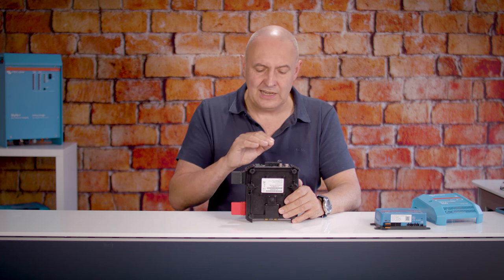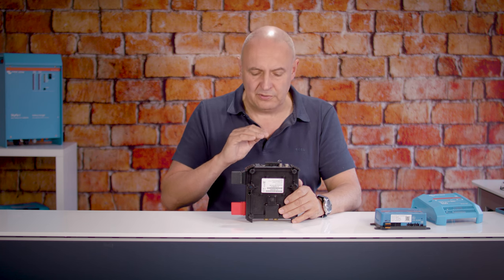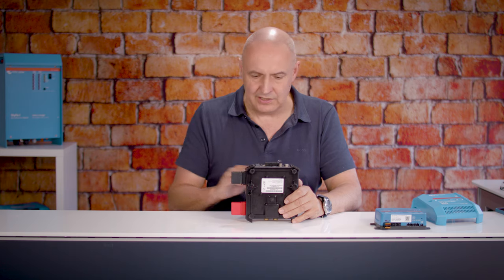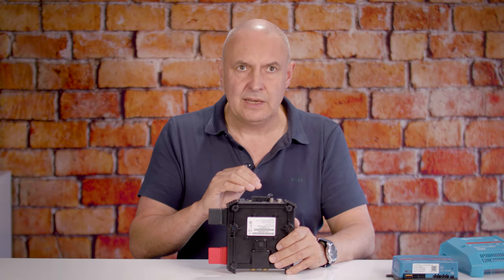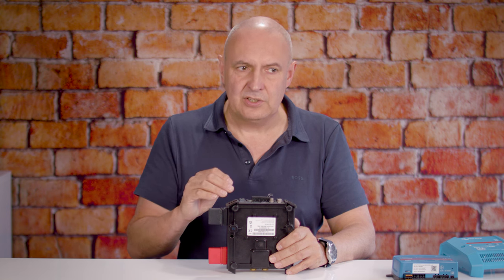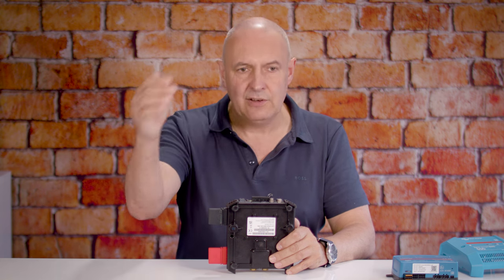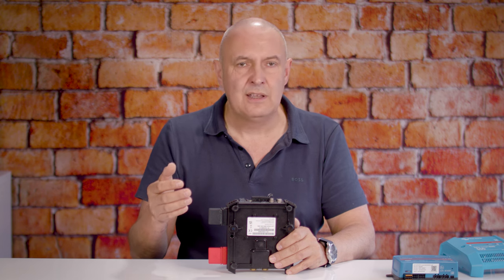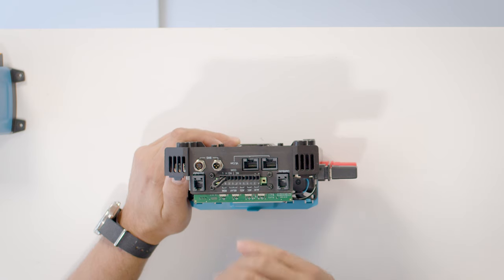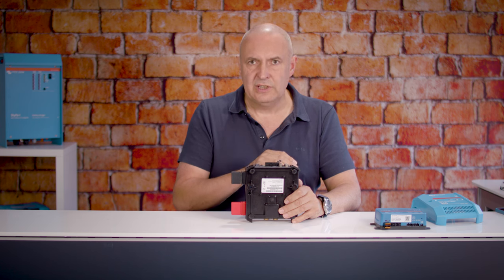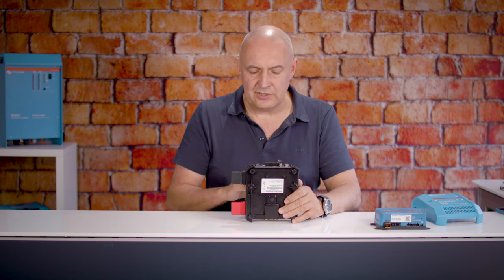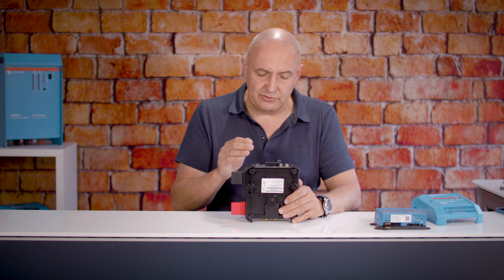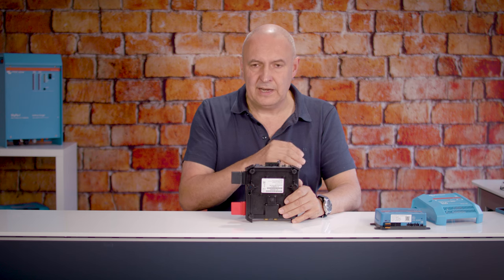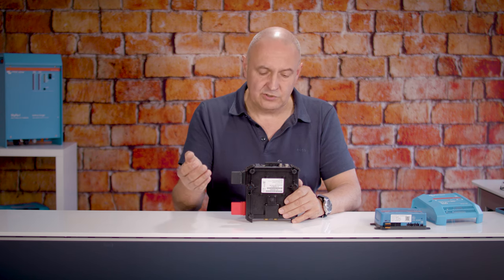So in other words, this allows you to turn off a charging device before the main contactor opens and kills the whole system. And it's great for controlling charging devices that cannot be controlled via VE.Can and through the Cerbo. So potentially a third party solar charge controller, for instance. Allow to discharge works in pretty much the same way, but on the low battery side of things. So it will allow you to turn off a load prior to the main protection contactor opening. And again, this is a volt-free contact that's available for you to wire in potentially through external relays, etc.